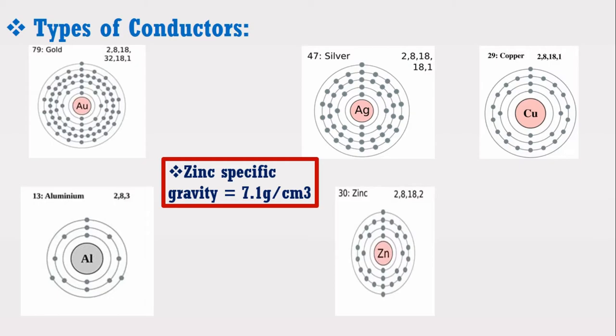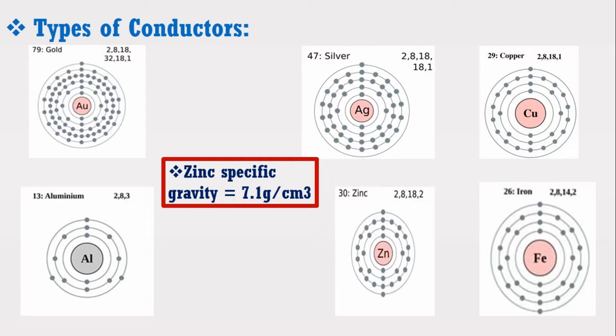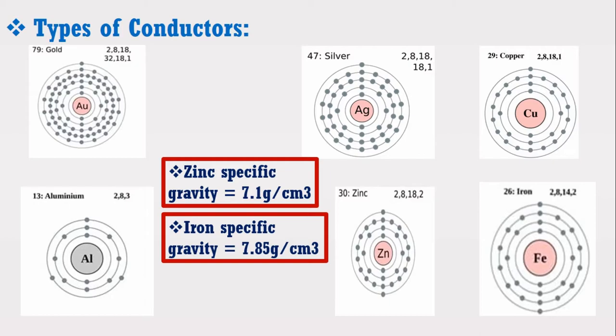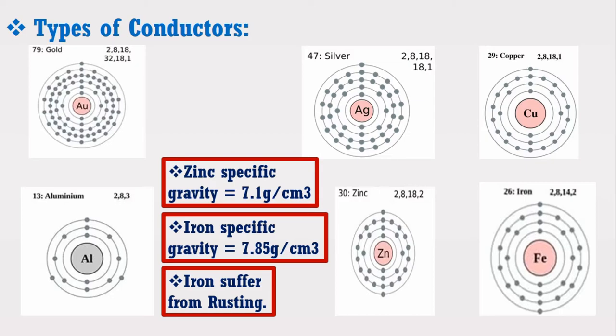Iron also has two electrons in its outer shell, meaning it is also a better conductor than aluminum. However, iron is also not used in the overhead transmission line. The reason is that iron has a very high specific gravity of almost 7.85 grams per centimeter cube. Due to this high specific gravity, its weight will be very high, which requires poles and towers of greater strength to carry its weight. This will further increase the total cost of the transmission line. Therefore, iron is also not used in the transmission line.